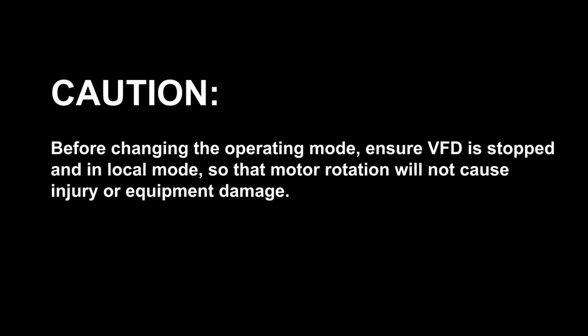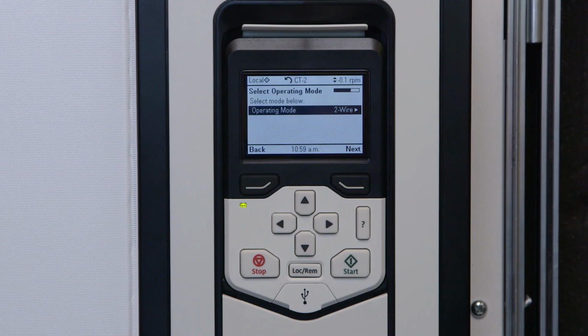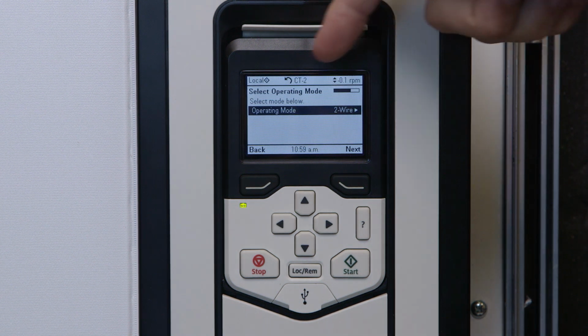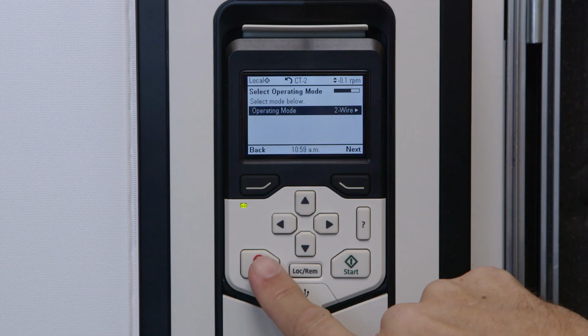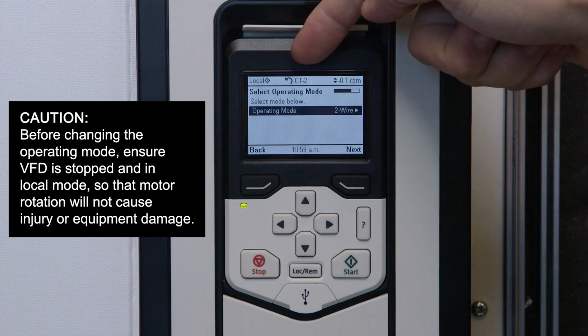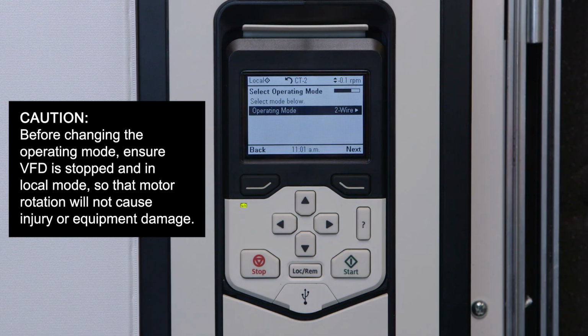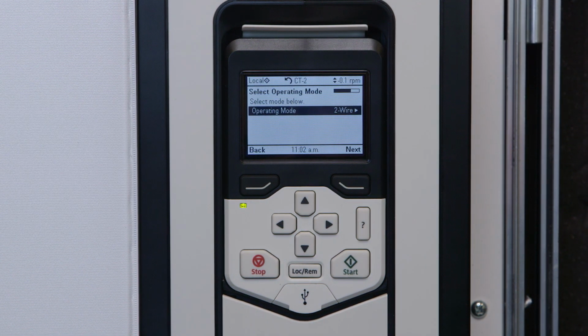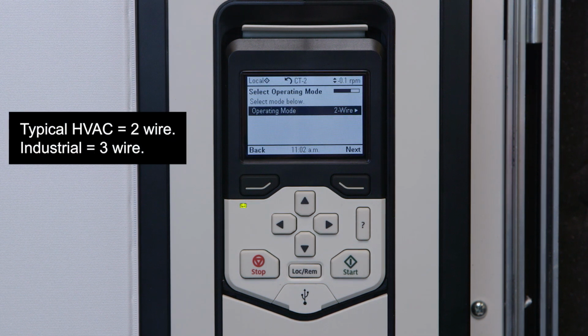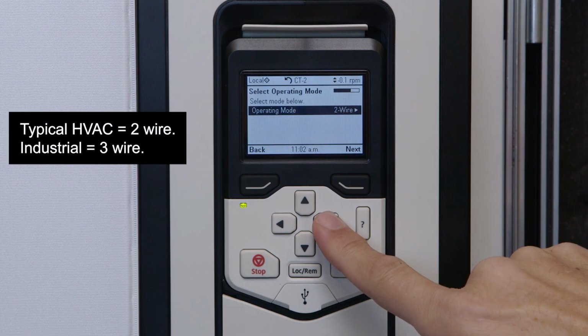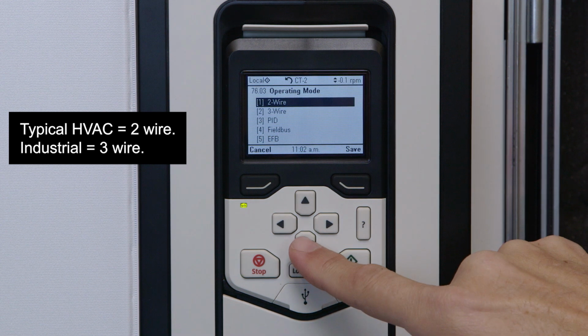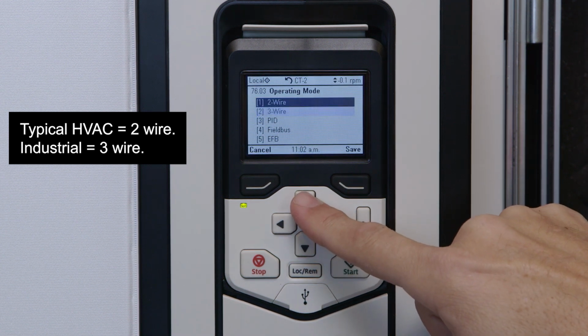Now that you've named the VFD, it's time to set up the VFD parameters that correspond to the control wiring. Before proceeding, it's important that you first ensure the VFD is stopped and in local mode. The display now prompts us to choose between either a 2-wire or 3-wire BMS start-stop command. Typical HVAC applications will be 2-wire, while industrial applications will be 3-wire.